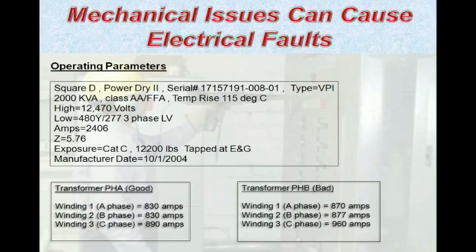If we look at the bottom two data fields here, you will see what I'm calling the good and the bad transformer, and you'll notice that the load demand on both units is very similar in nature. So we have the same types of current loading on each unit, but we have a qualitative difference on one of the coils with the bad unit.